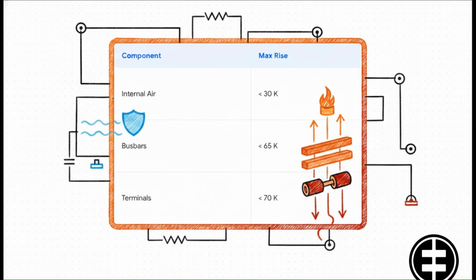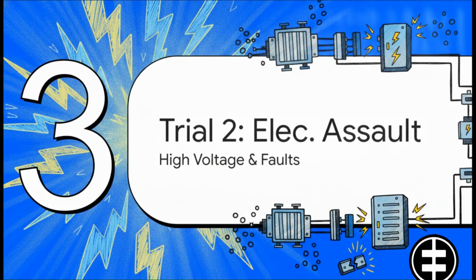Testers use thermocouples to monitor all the critical areas and verify specific limits. Now, while the internal air is capped at that 30 Kelvin rise, the bus bars are actually permitted a 65 Kelvin rise, and cable terminals can get up to a 70 Kelvin rise. But here's the catch. The current ratings for these components are only valid if the temperature surrounding them stays strictly within these exact boundaries. Okay, on to Section 3, Trial 2, Electrical Assault, High Voltage, and Fault Currents.